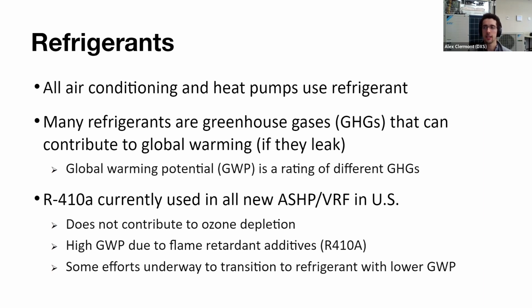Now it's still possible to buy recycled R22 that's been reclaimed from existing equipment, or to use drop-ins as well, like Bluon, which is R-458A. The phase out of R22 is one of the most successful global treaties that was agreed on. If we go back to R410A for a little bit, the refrigerant itself is not too bad, but it's the flame retardant additives in the refrigerant that make it have a high GWP. And there are efforts to transition into lower GWP refrigerants, which we'll get into now.